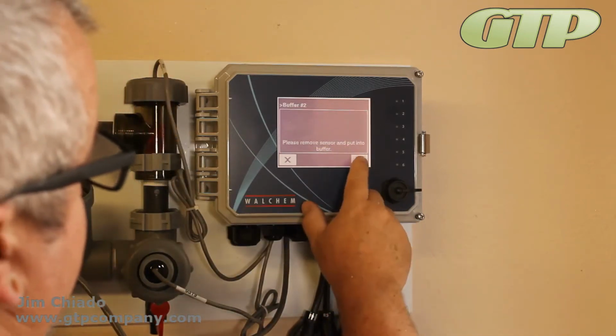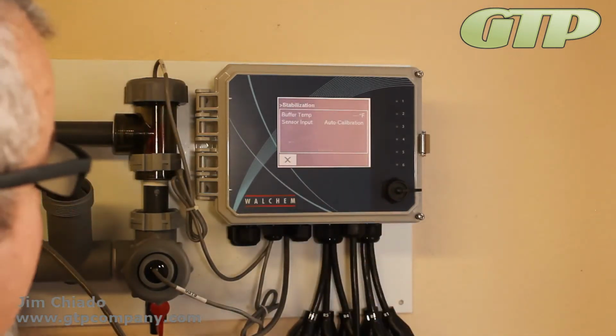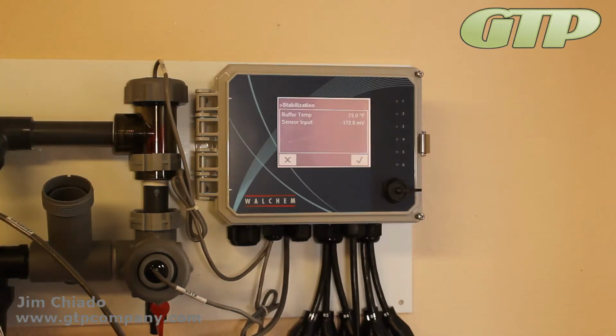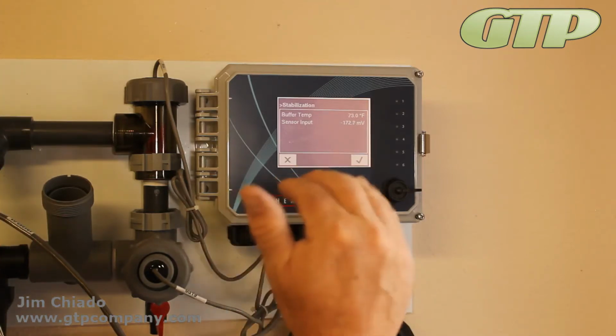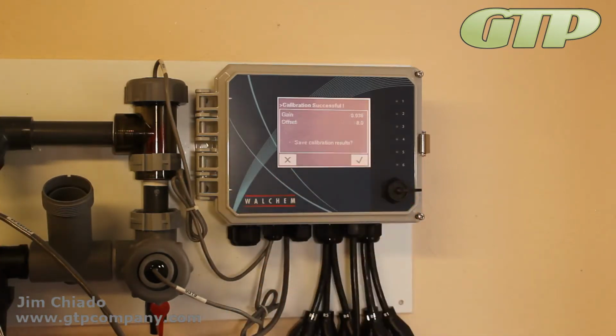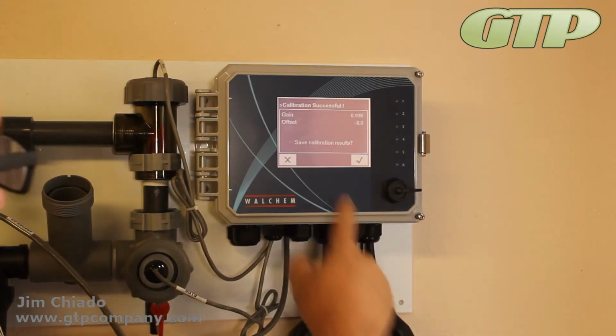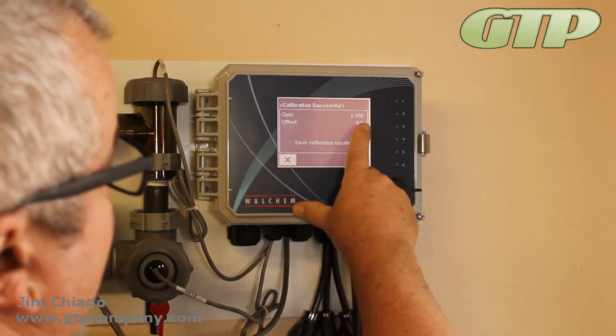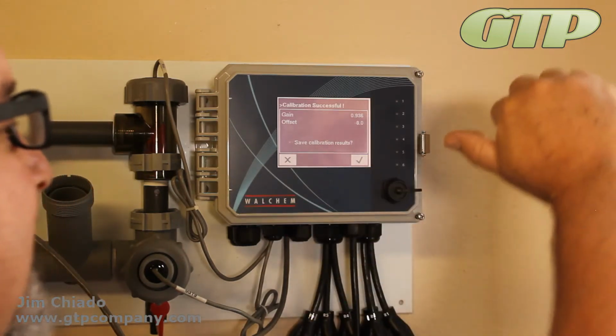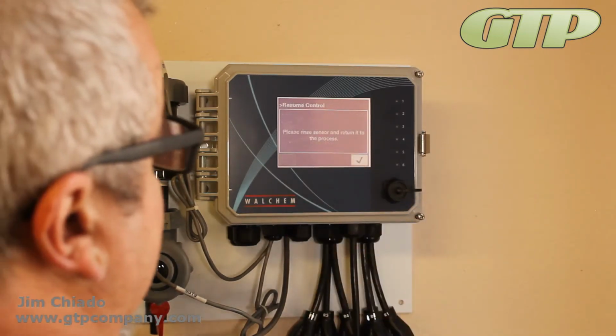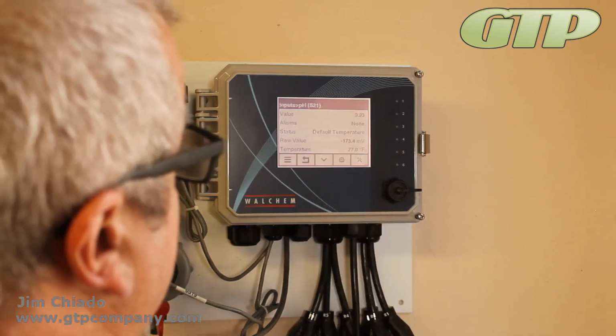I have to check. Now it tells me to do what I just did. Okay, and you see -10 for a high pH, or negative numbers, and then a low pH for positive numbers. Save the calibration. You see the gain and the offset. So now it's trying to set the slope. Calibrations are good. Okay, return it to the process.